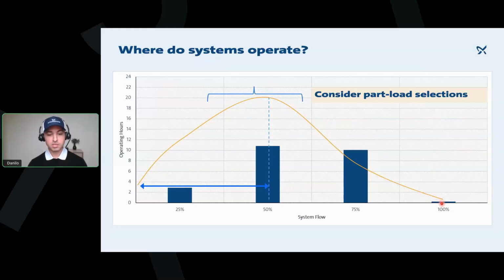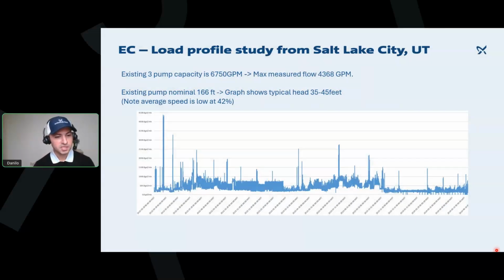if we ever get to 100% load, right? And then after identifying that, the engineer is always also gonna add that safety factor and it's gonna upsize them a little bit more. What happens is now you run your pumps too far out of the curve at part load conditions, which means most of the time you're gonna be outside of your preferred and even maybe the allowable operating range, right? I have an example. Bob's gonna like this one because this is from Salt Lake City.